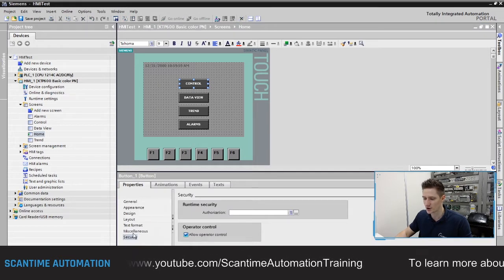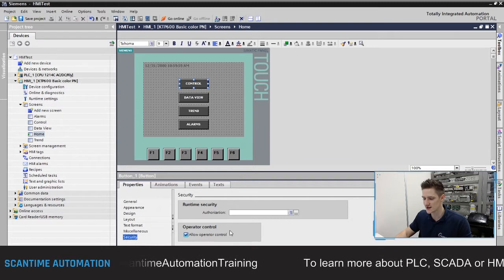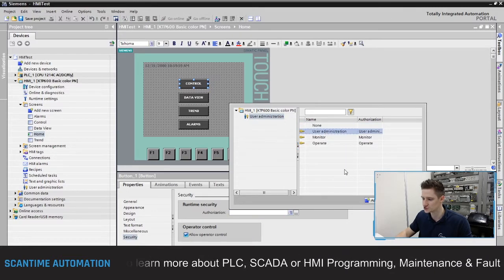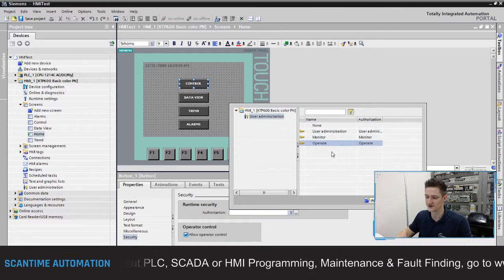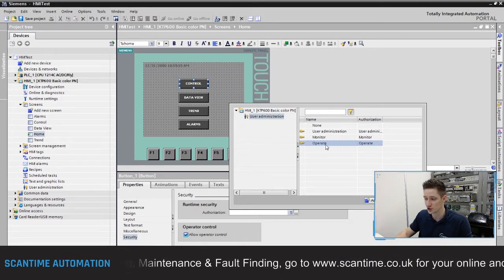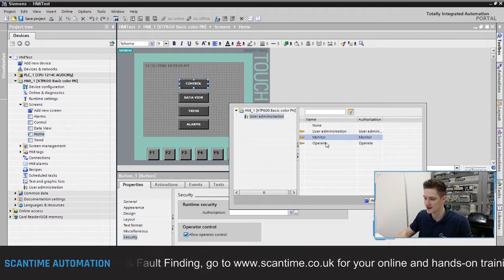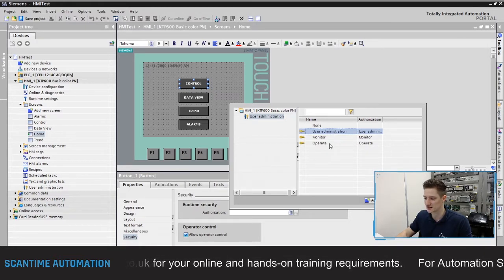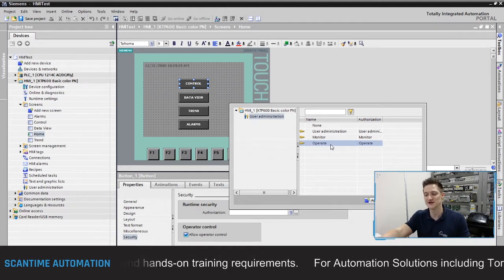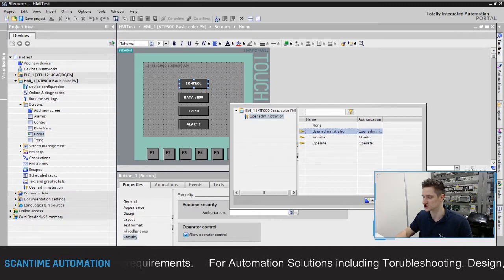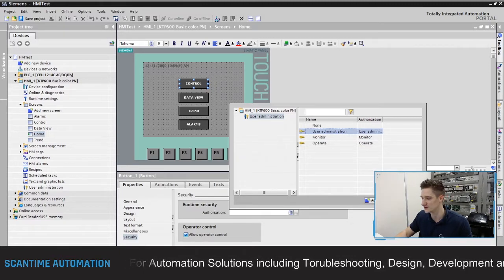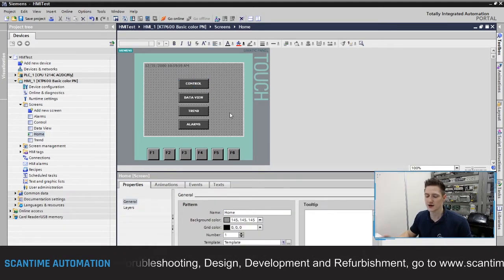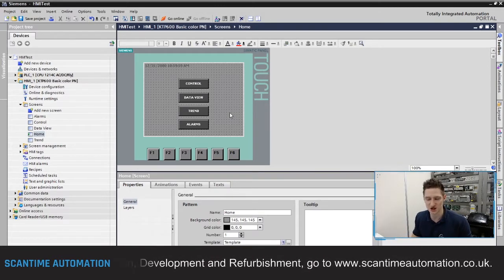To restrict access to the control screen button, click the button, go to Properties, and at the bottom you'll find Security with 'Runtime Security Authorization'. Click the three dots and you'll see User Administration, Monitor, and Operate — our three security levels. I'm going to check 'User Administration' so that operators can't access that screen. Only maintenance-level users, who have User Administration rights, will be able to open the control screen.